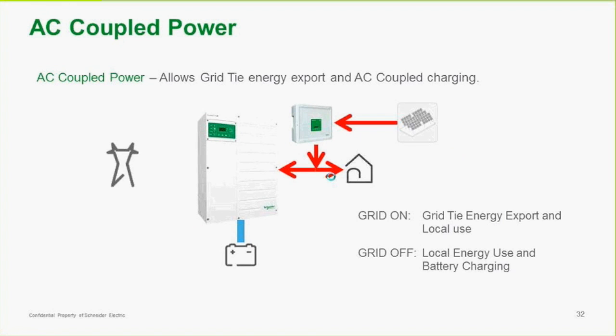So we're getting into AC coupled power now, and AC coupled power allows a grid-tied energy export and AC coupled charging. So the XW Plus is a grid-forming inverter. Most of the time, those grid-tied inverters need to see a grid, and in this case the XW Plus would provide that. The grid-tied inverter and the XW Plus are both connected to the same AC bus. So what happens here is, well, we'll talk about that in a minute as far as the AC coupling goes.